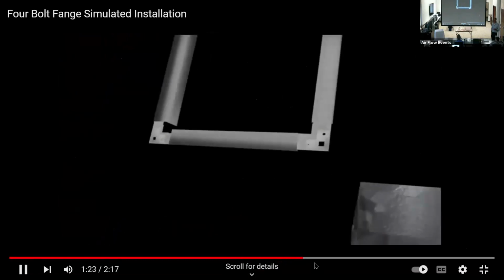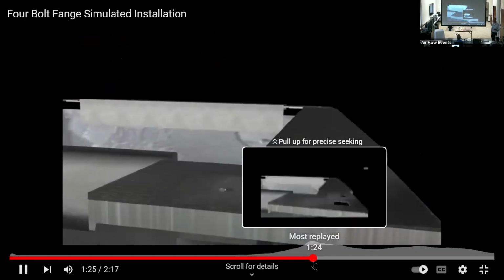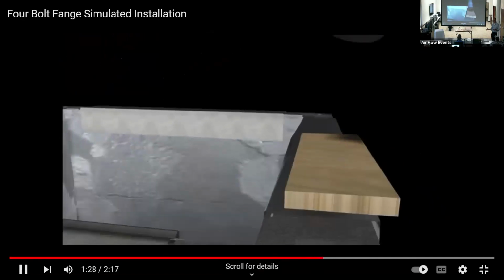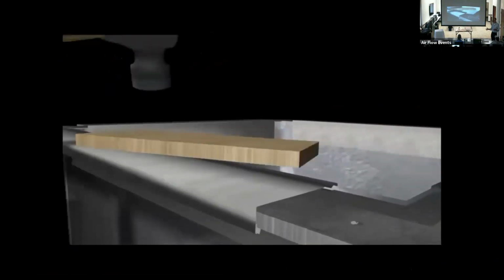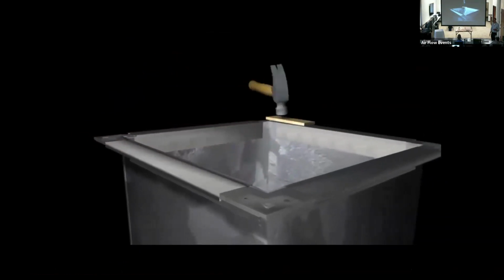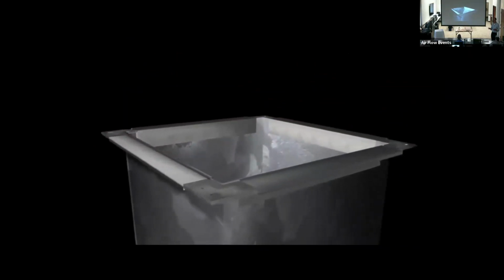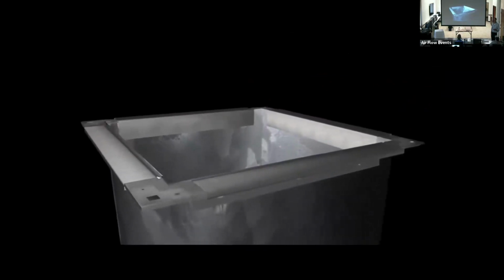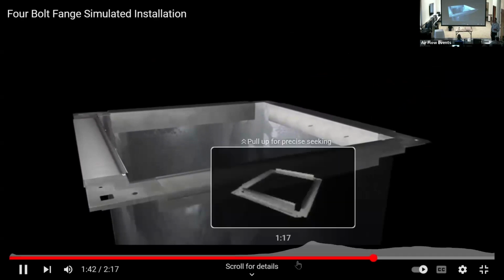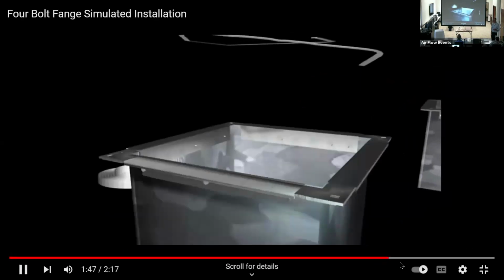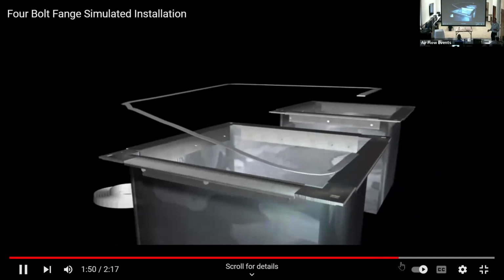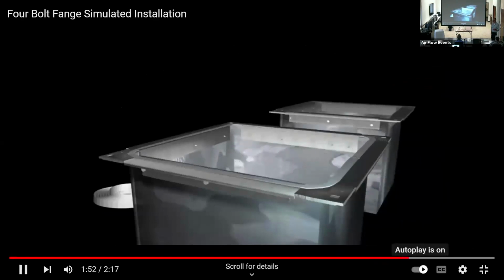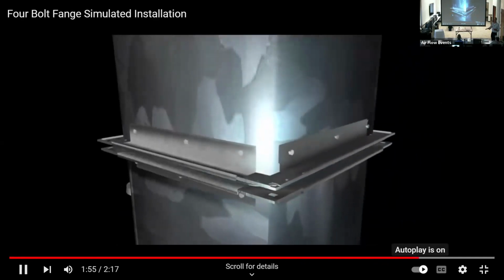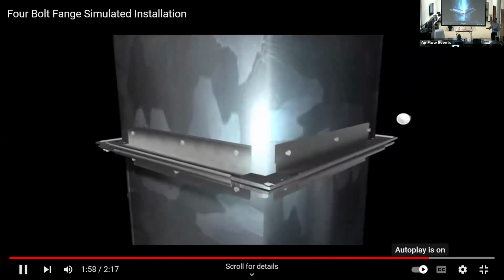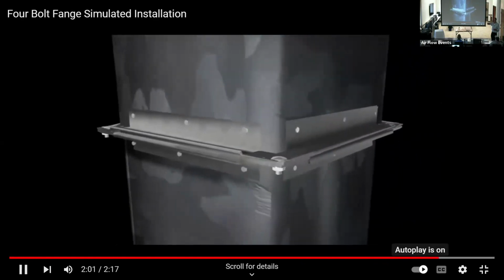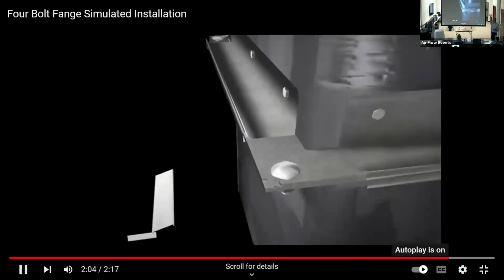Now we're going to put it on the top of the duct. It should be kind of a snug fit, but you notice even though we're banging this thing together, it still isn't a sealed up system. There's caulk on the inside of those. There is caulk inside those, and there should be, right? Right, so this is just screwing. Sienna, we can go a little bit quicker now. Then we're going to put some butyl tape on, and then we're going to bring over our second section. This is how it goes together, and all high pressure ductwork is built this way. Then we're just bolting it together, and then we have this tool that bends that, I don't know what you call it, that C-clamp over. Cleat.